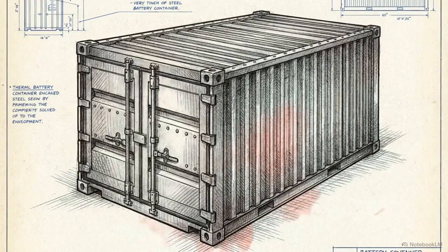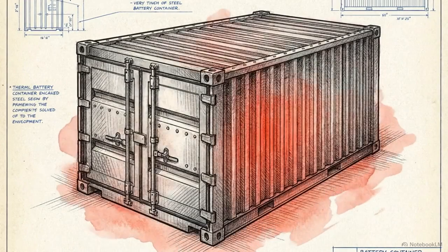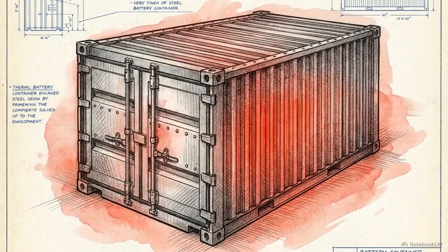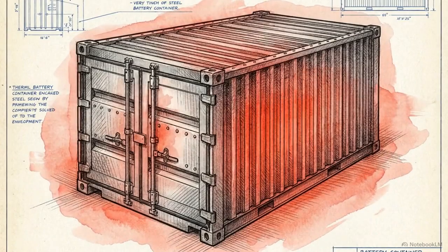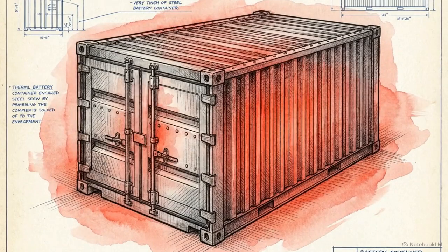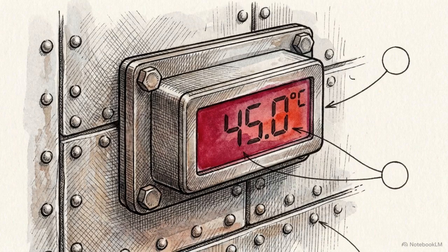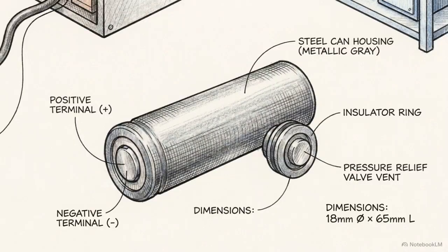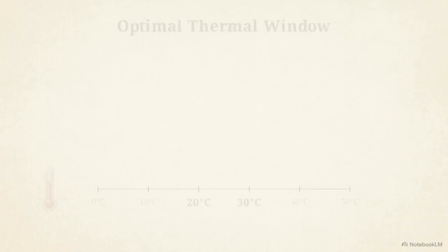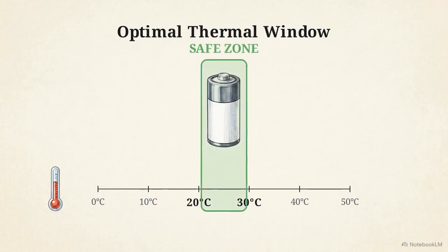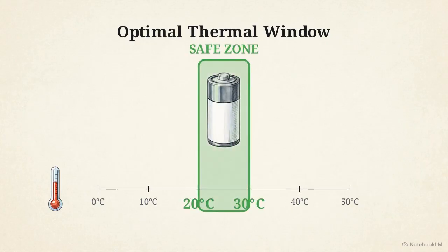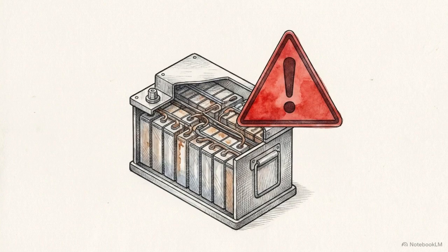At 500 kilowatts, a 3% inefficiency creates 15 kilowatts of continuous heat generation. Because this reaction is happening inside a tightly sealed steel container, that internal heat begins to compound rapidly. Lithium-ion battery cells operate under a strict physical constraint. To function safely, they must be kept within a rigid temperature window of 20 to 30 degrees Celsius. Exceeding that 30-degree threshold carries escalating physical consequences.